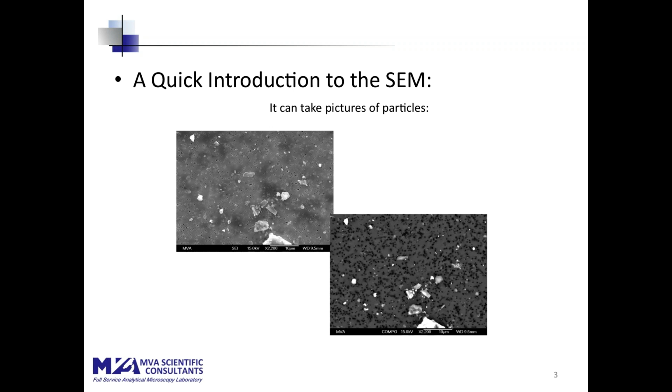The advantage of the backscatter electron mode is that it highlights the Z contrast, or the atomic number of the particulate, so that you can see that this particulate, which is principally aluminosilicates, shows up bright against the background of a polycarbonate filter, which is principally carbon and oxygen.